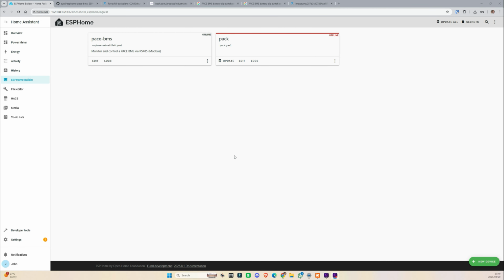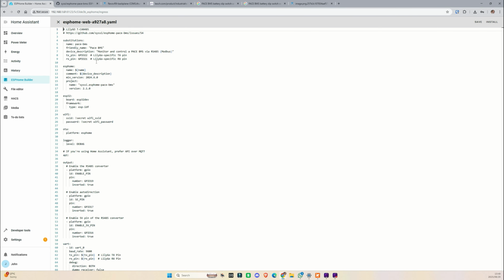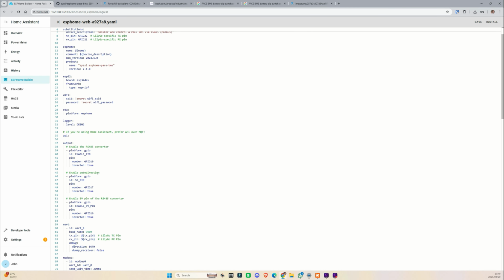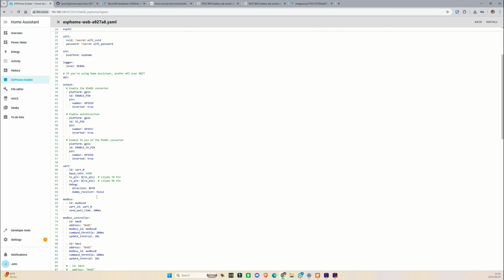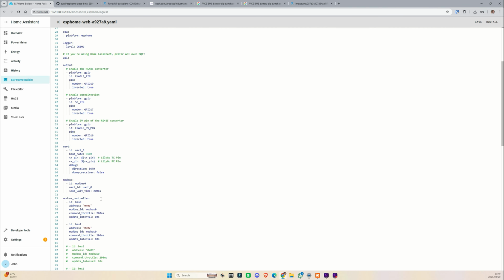Okay, so the first thing we want to do is just check that our dip switch settings, that our battery IDs are at the correct address for querying the Modbus controllers. We're going to be using address 1 and address 0. They need to be at those addresses — those you set on the dip switches on your battery.